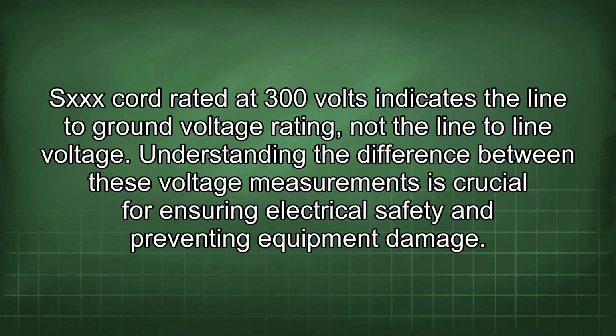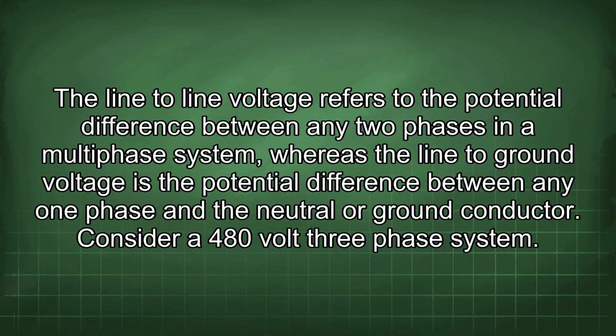Sxxx cord rated at 300 volts indicates the line-to-ground voltage rating, not the line-to-line voltage. Understanding the difference between these voltage measurements is crucial for ensuring electrical safety and preventing equipment damage. The line-to-line voltage refers to the potential difference between any two phases in a multi-phase system, whereas the line-to-ground voltage is the potential difference between any one phase and the neutral or ground conductor.